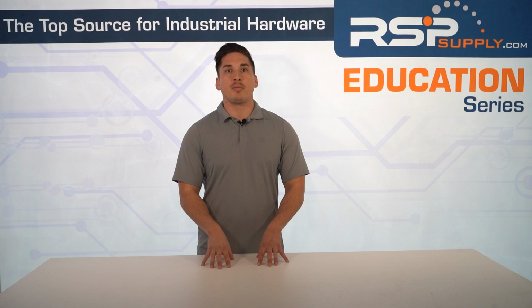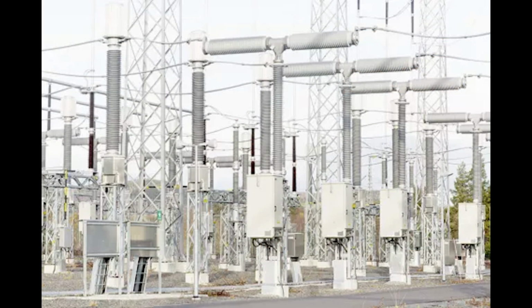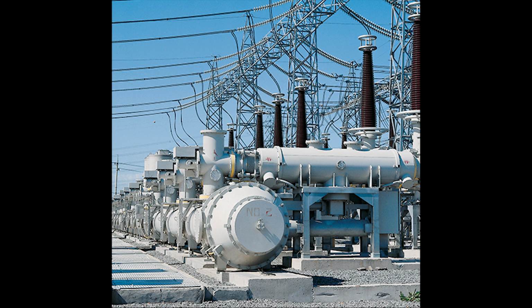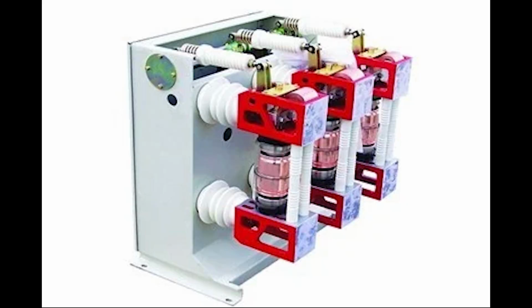Some arc interrupting mediums are as follows. There's air insulated switchgear, or AIS. It's very cost effective, but it's very space intensive, takes up a lot of room. Gas insulated switchgear is a lot more compact, a lot more efficient. It uses something called SF6 gas for insulation. There's also vacuum circuit breakers, or VCB, and these use vacuum for arc extinction, offering durability and low maintenance.